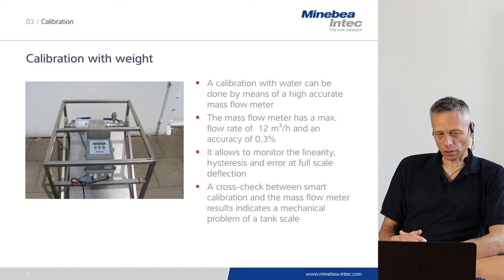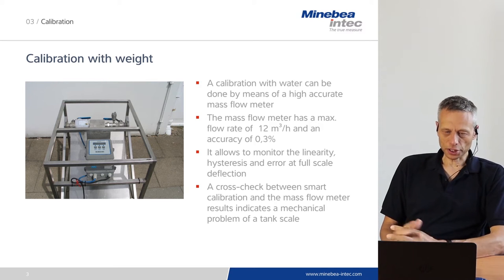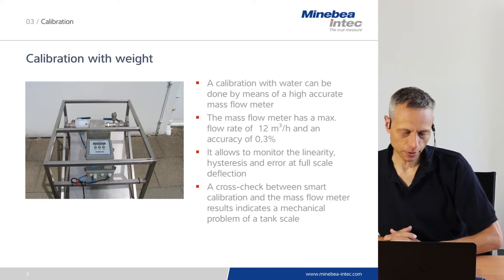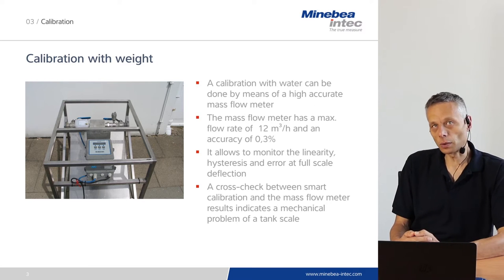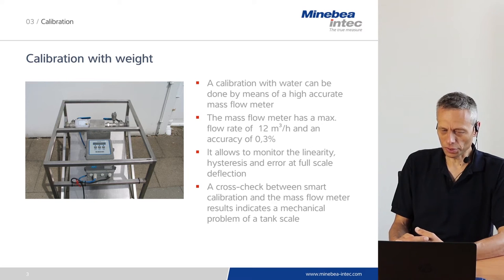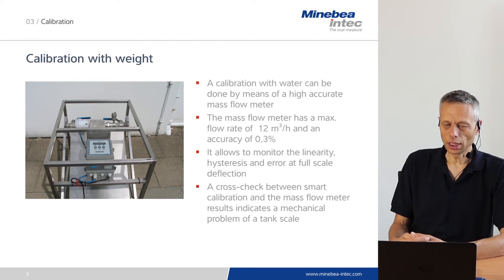Let's look into different alternatives of calibration with weights. One option is calibration with water, which can be done by means of high accuracy mass flow meters. The mass flow meter shown in this picture has a flow rate of 12 cubic meters per hour and an accuracy of 0.3%. So you can imagine that filling a high capacity silo with water can already take several hours — for example, a 50 cubic meter silo will take at least 4 hours filling time. The accuracy of 0.3% is already good for a flow meter, but sometimes the accuracy required of a process vessel scale needs to be higher.